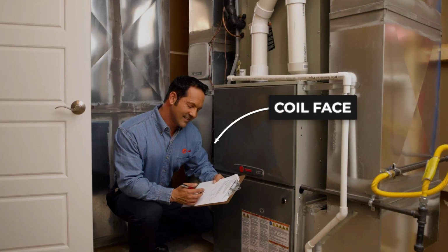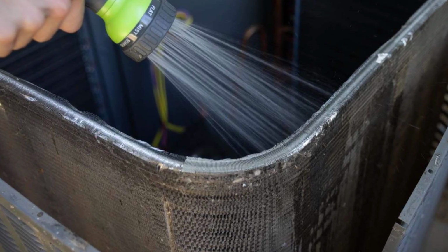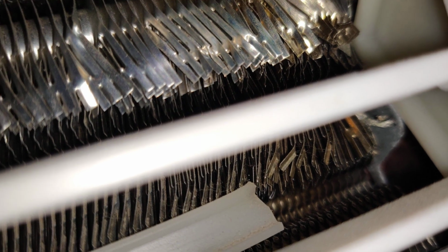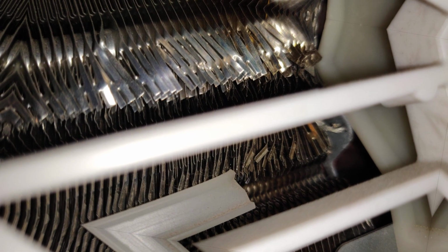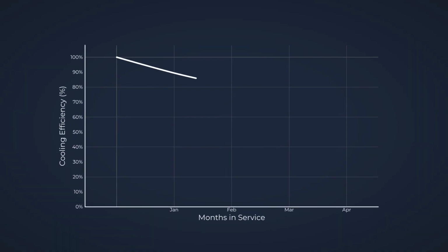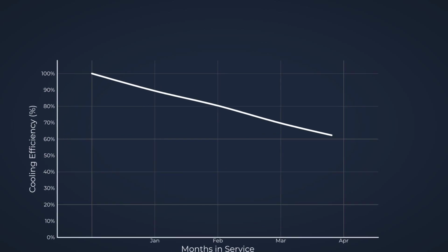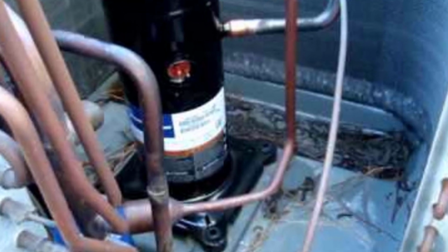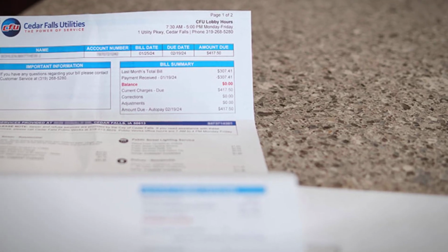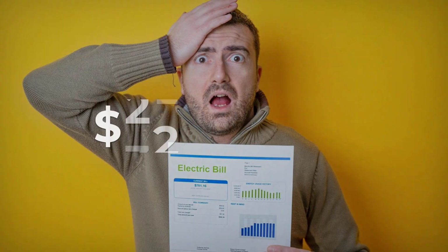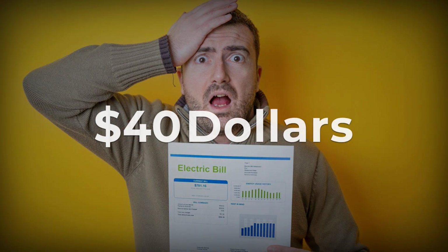Trane's own maintenance literature emphasizes specific cleaning procedures for microchannel because the standard shop vac and hose routine can bend fins and create more problems than it solves. This is where the trouble often begins. Performance drops. Efficiency falls. The compressor works harder to compensate. The meter spins faster. You do not notice until the electricity bill arrives, $40 higher than last summer.